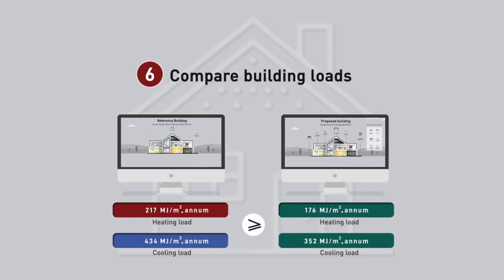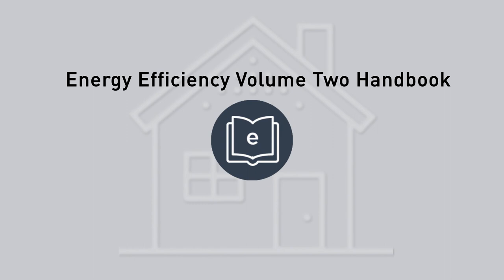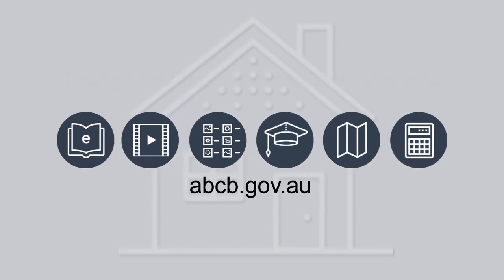And lastly, in step six, compare the reference and proposed building's heating and or cooling loads. If the proposed building has a heating or cooling load which matches or is less than the reference building, then compliance is verified. If not, make design adjustments and repeat from step four, or use a different assessment method. This verification method is clearly outlined with worked examples in the handbook Energy Efficiency NCC Volume 2. The handbook and other resources are available from the ABCB website.